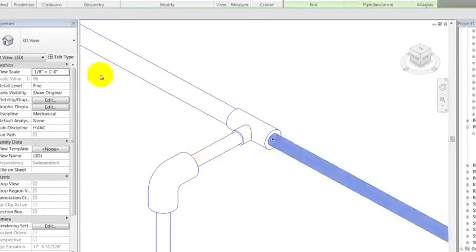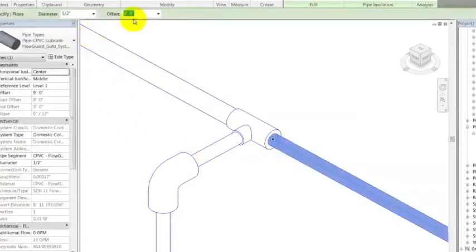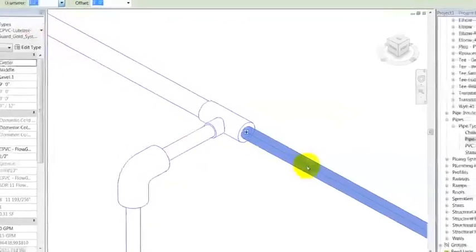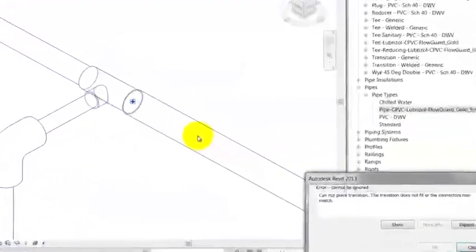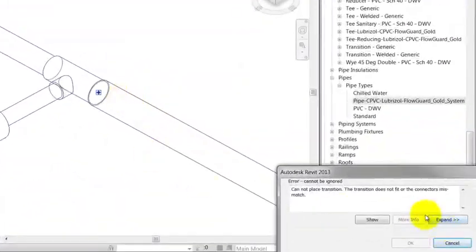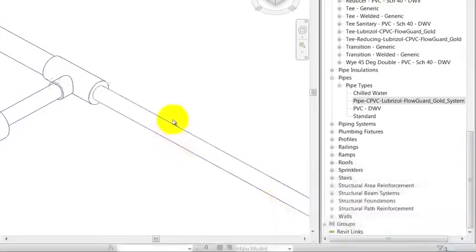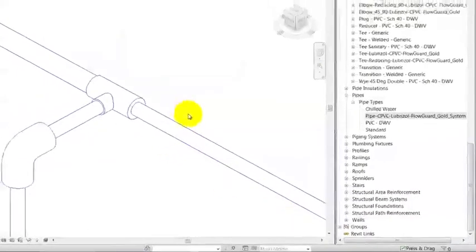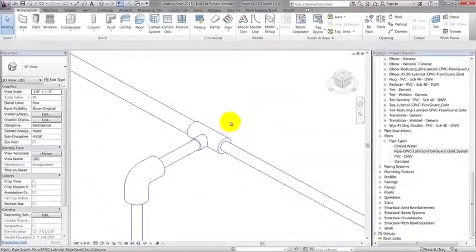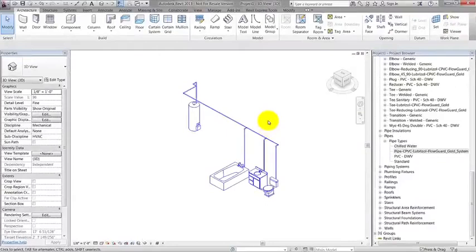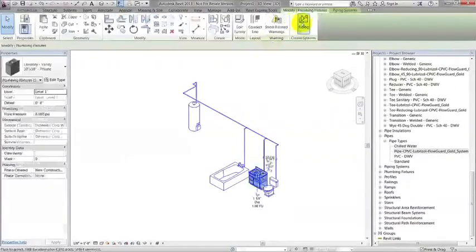Let me show you what would happen if I changed a pipe to an unavailable size. The error appeared because the fittings are not supposed to work with the size selected. This is the expected result, and I would need to double-check this product's information to confirm all the diameters used in the system, especially in the connections, are correct.